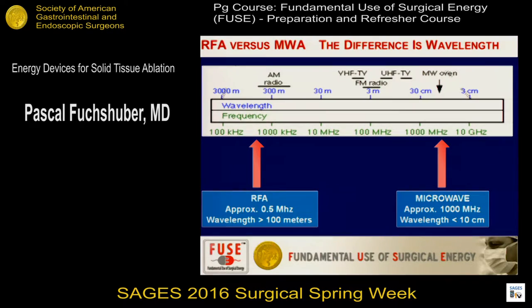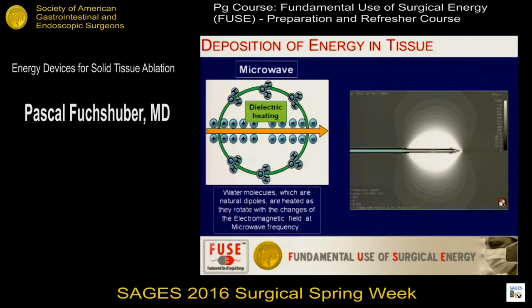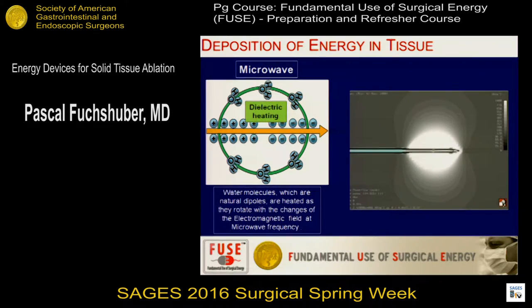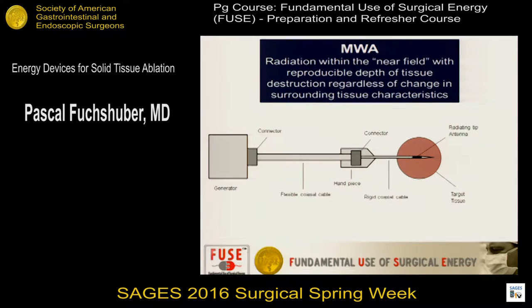In microwave, the wave is about the size of the tip of the electrode. That causes a completely different tissue effect — it's not based on ionic back-and-forth kinetic heating. Instead, it is based on water molecules, which are natural dipoles, being heated by rotation at 1,000,000,000 times per second. This creates the change in tissue temperature — so-called dielectric heating. This is what the spatial distribution looks like at the tip of a microwave antenna.